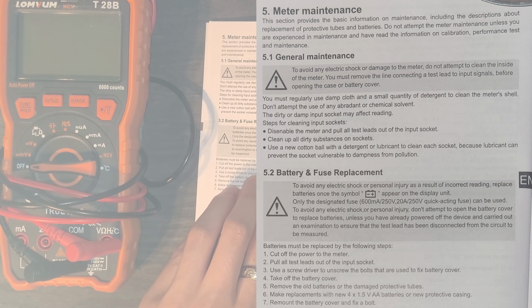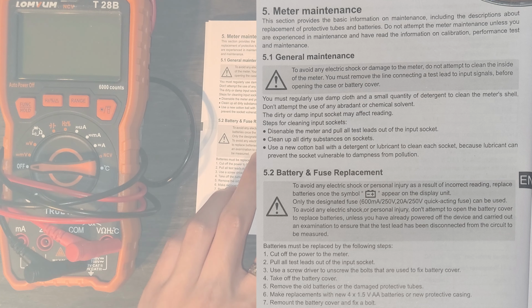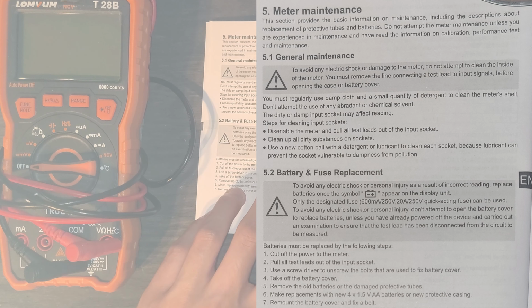Now, battery and fuse replacement. To avoid electrical shock or personal injury from an incorrect reading, we should replace the batteries when we see the symbol appear, which we've seen before. Only the designated fuse, 600 milliamps 250 volts or 20 amps 250 volts quick-acting fuse, should be used. To avoid electric shock or personal injury, don't attempt to open the battery cover to replace the batteries unless everything has been powered off and you've confirmed the leads have been disconnected from the circuit being measured.